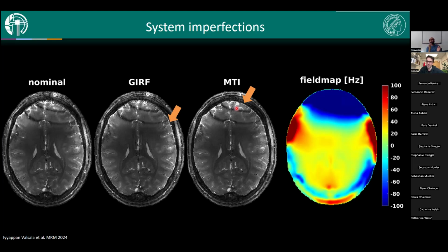Of course, you can measure for some time and fill the rest with the GIRF correction, but you have to do some kind of blind spot interpolation to make this work, and you need a coil which can do that. This we didn't have at the time. Okay. So it's just GIRF and B0 correction. This is very standard B0 correction.